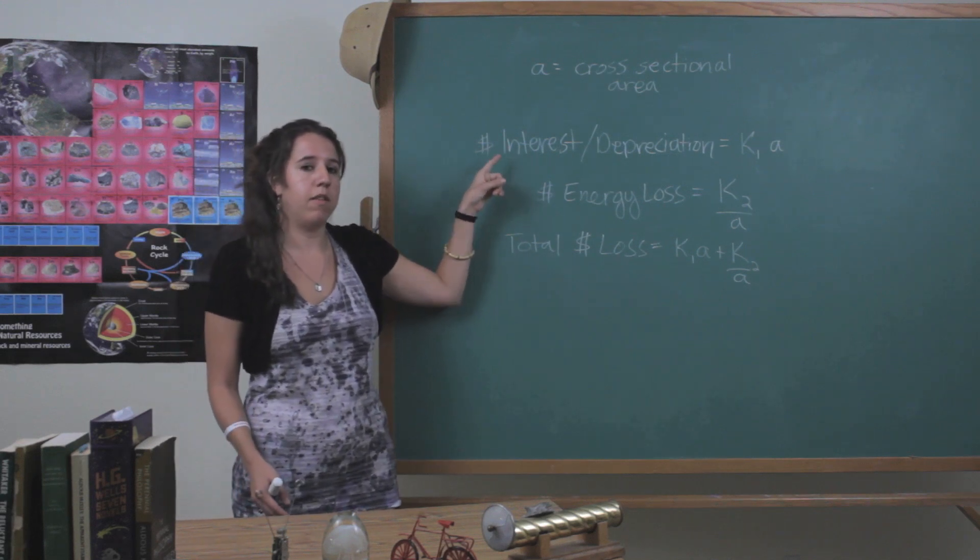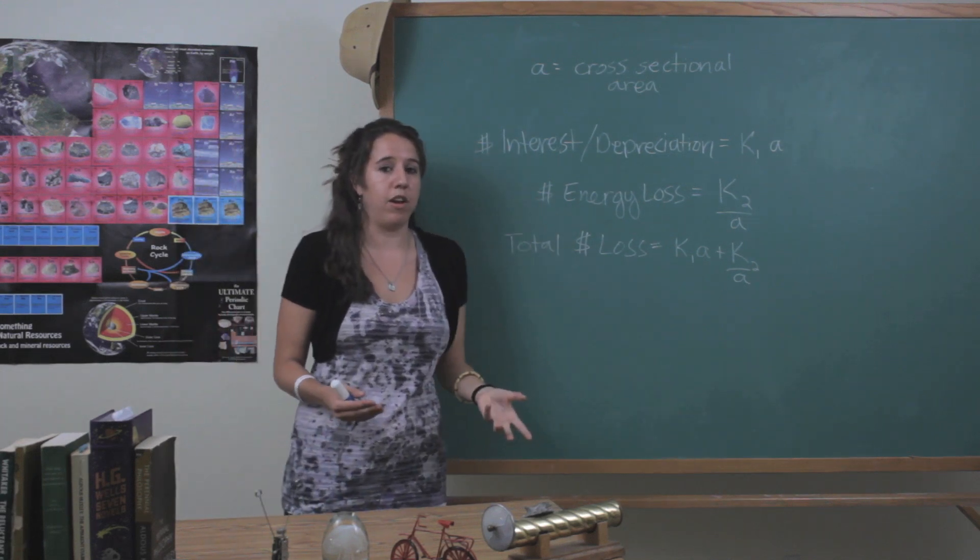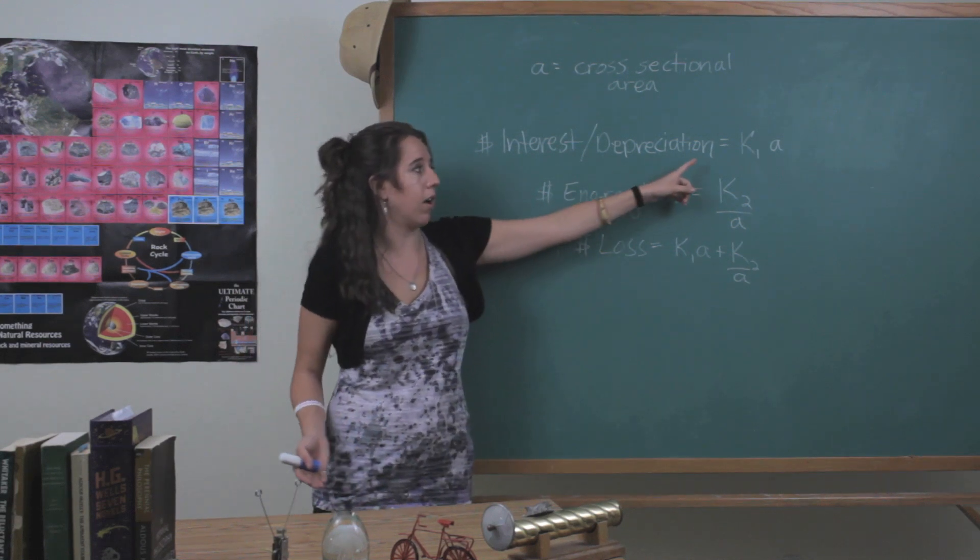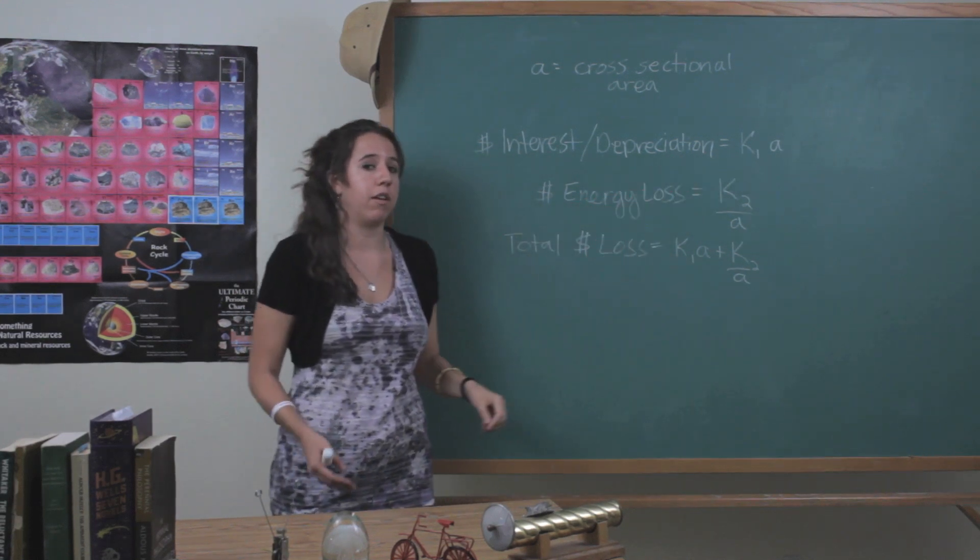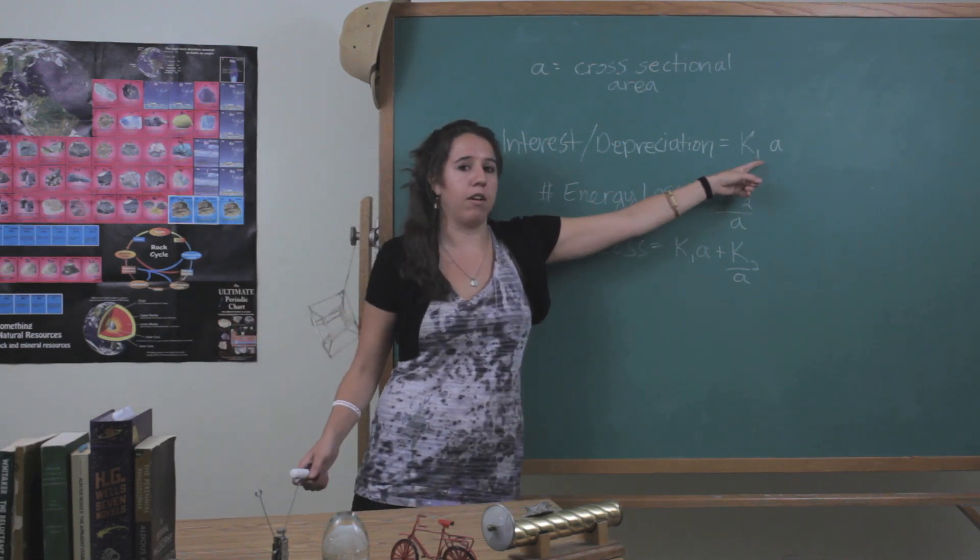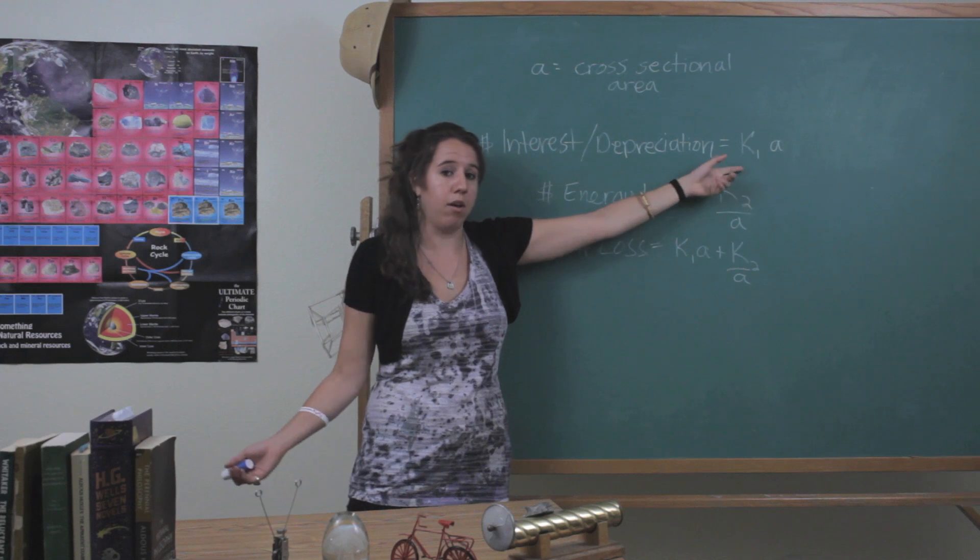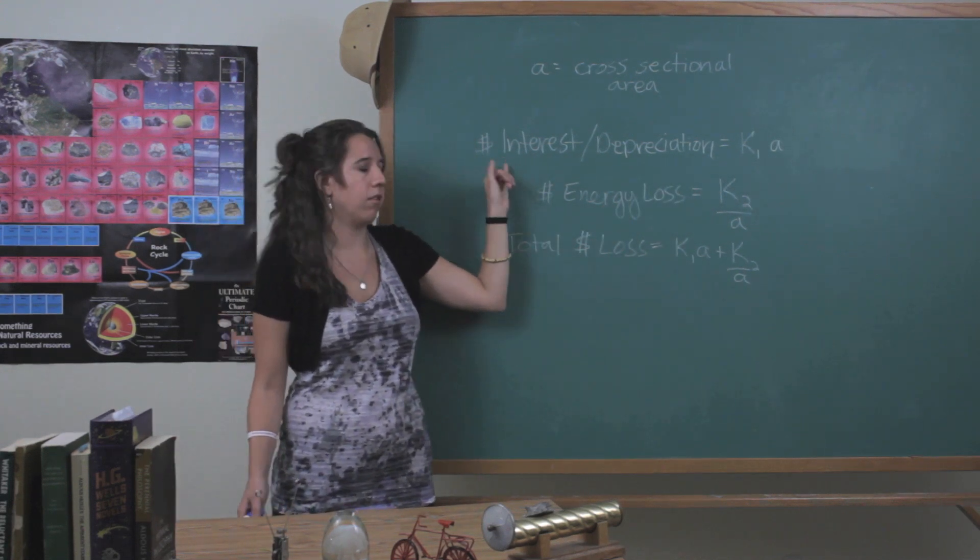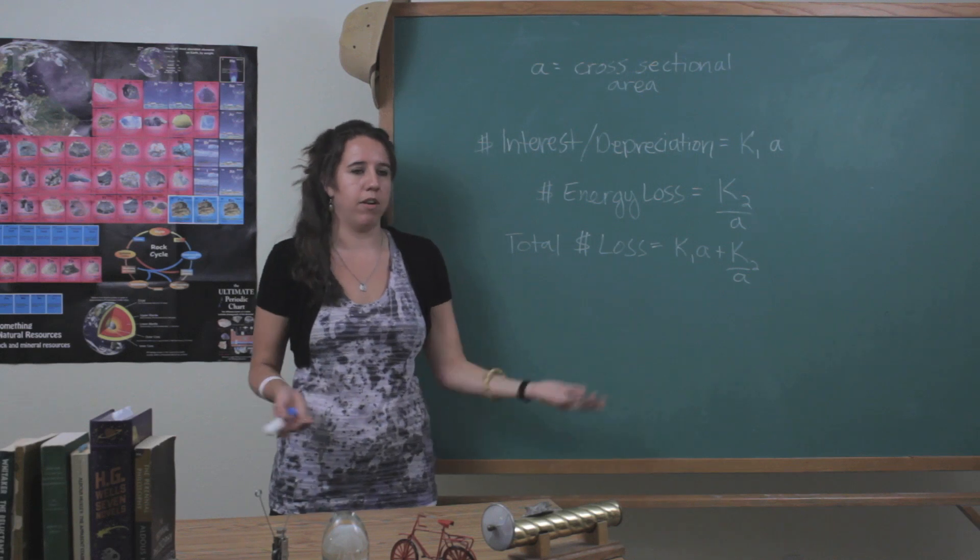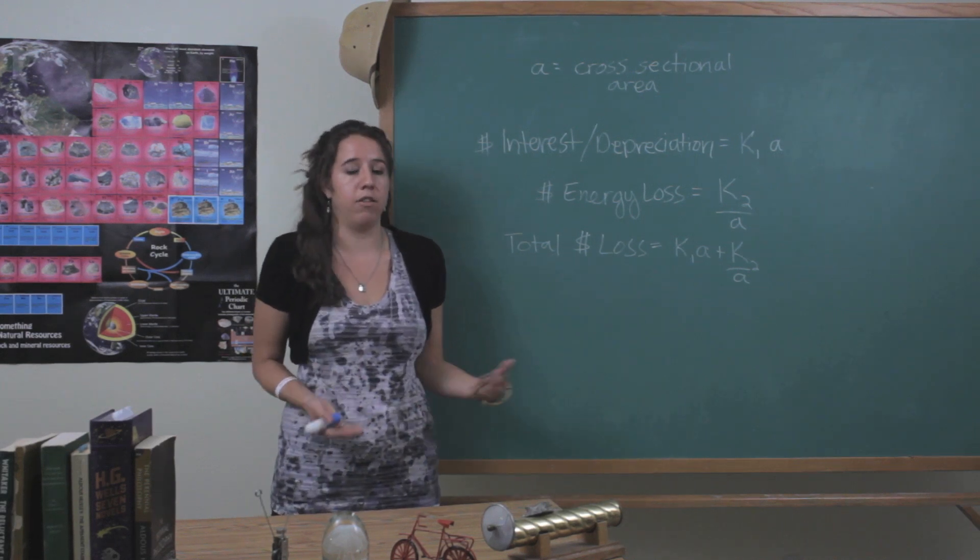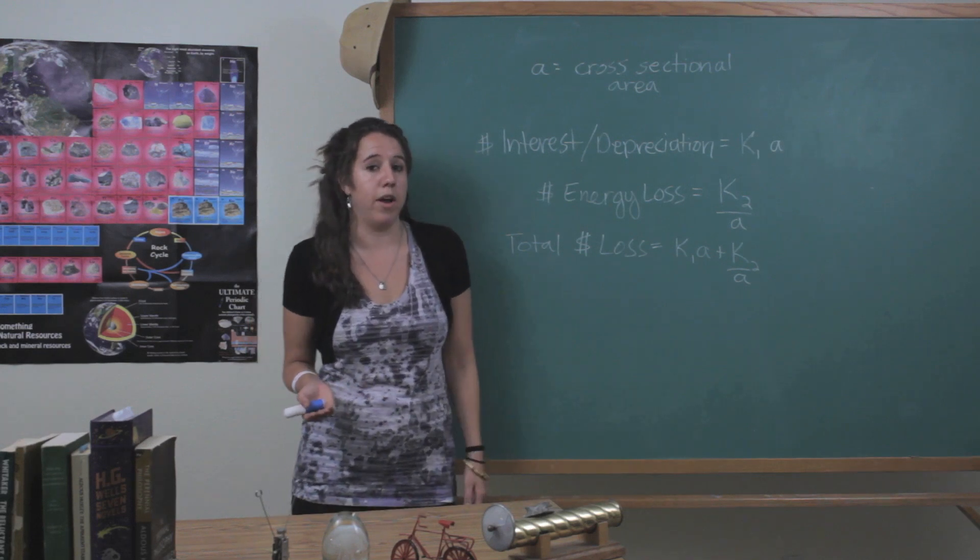So this first one, the cost of interest and depreciation on the line that you've chosen to use is going to be directly proportional to the cross-sectional area of the wire. And what that means is you take the cross-sectional area, multiply it by some constant, we call it K1 here, and then that's going to be how much money you're losing yearly or whatever time you like in interest, depreciation, and the cost, the initial cost of the investment in the wire.